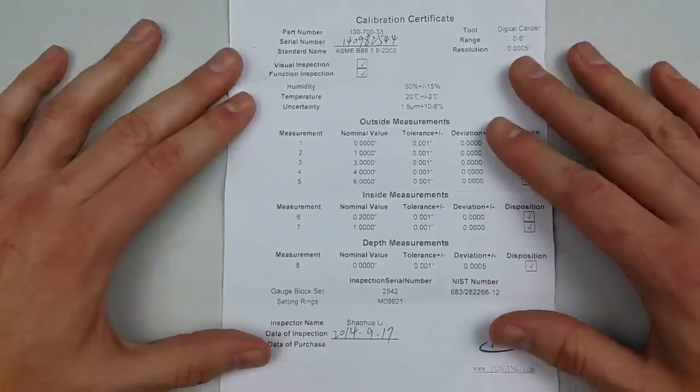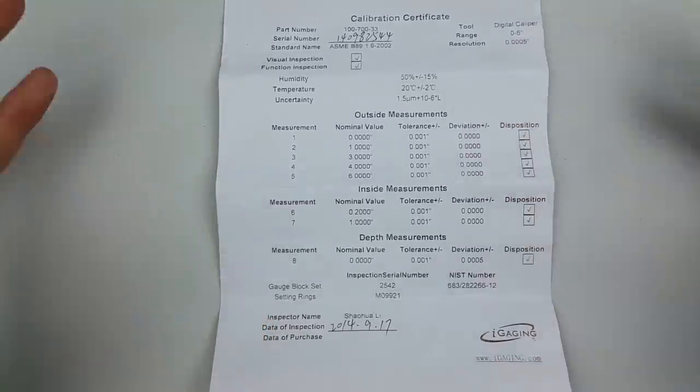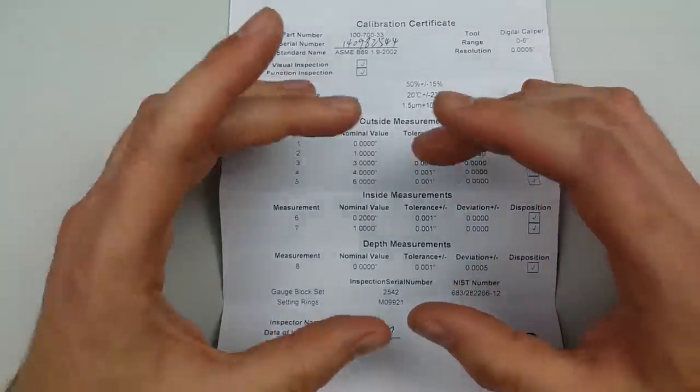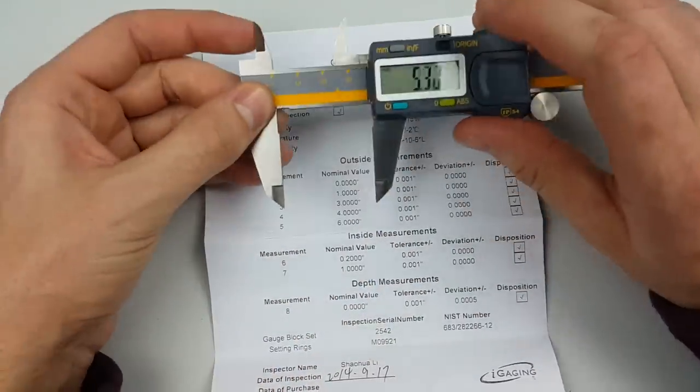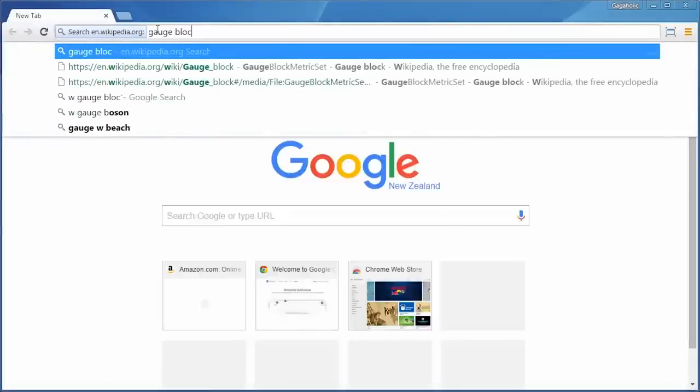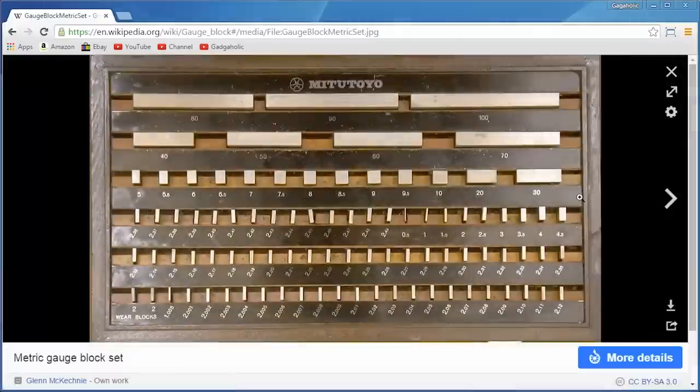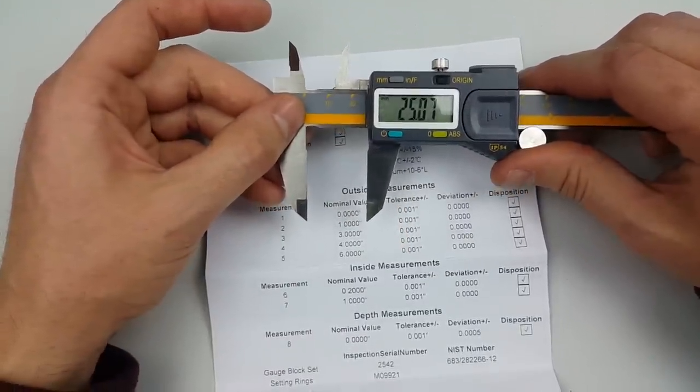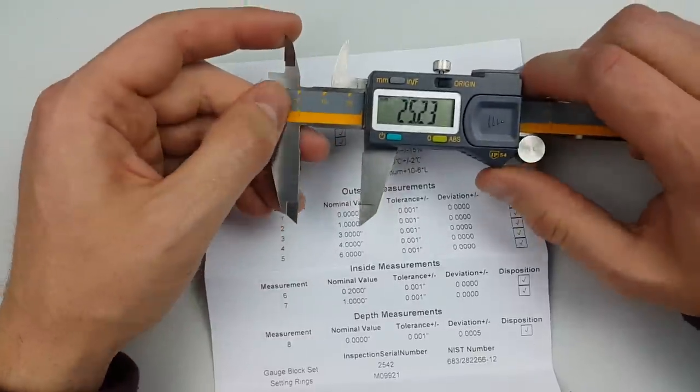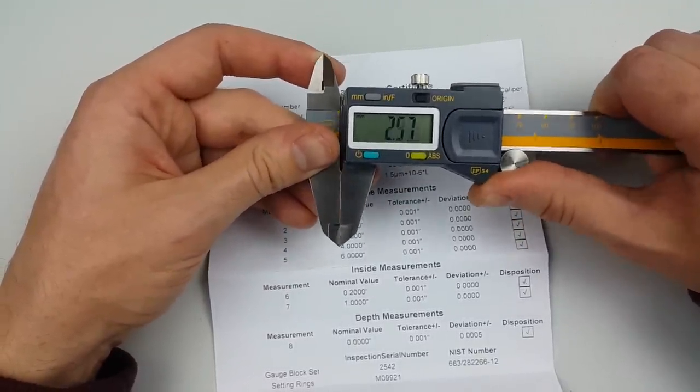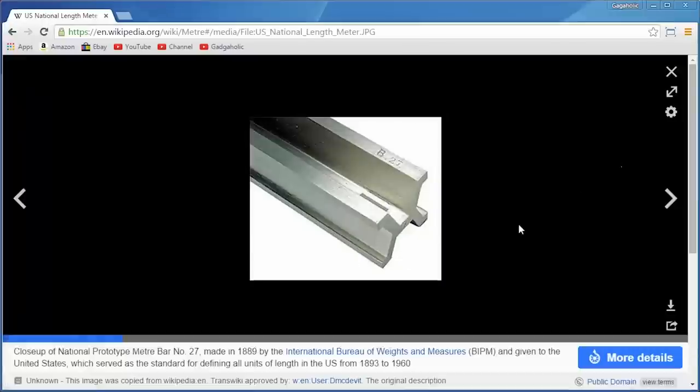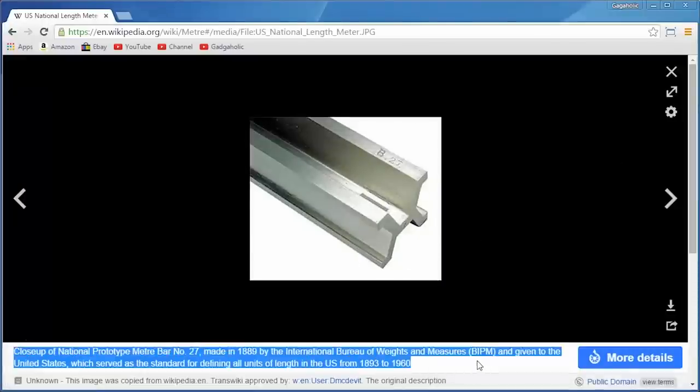Now, this isn't a traceable certificate. What this means is that we don't know, or we can't verify, that the gauge blocks they were using to do these measurements. So they get a block that says it's exactly, let's say 25 millimeters, and then they check that this measures within the specified tolerance as 25 millimeters. Now, what happens if the block they're testing isn't in fact 25 millimeters, it's got rubbed or shaved off a little bit. So then this would be calibrated to an incorrect measurement. For my purposes, I don't need traceability. If you're producing products and your quality control will cost you money if it's not right, then you want a traceable certificate that essentially tells you what lab the equipment was calibrated against, and you can basically trace it all the way back to the metric standards in a vault in France.